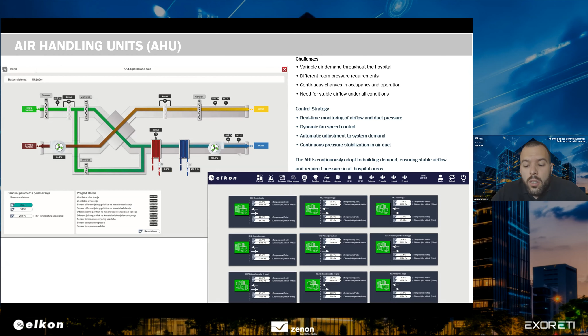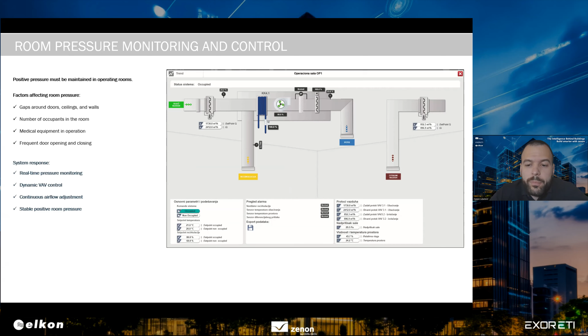So, as I said, inside the hospital, especially inside operating rooms and ICUs, a very big and crucial factor is pressure inside the room. The pressure is affected by the gaps around the door, ceiling, walls, number of occupants in the room, medical equipment that is currently in operation, and frequent door opening and closing. So in order to achieve a stable pressure, real-time pressure monitoring is required, dynamic VAV control, and continuous airflow adjustments had to be made to achieve stable positive room pressure. Besides that, obviously, inside these kinds of rooms, temperature control is absolutely mandatory, and humidity control as well.